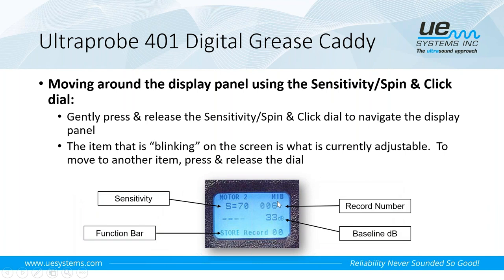And then across the top, where we see motor two, and then the MIB, or the motor inboard, this is the machine name and the point name. However we name the route or name our points in the software, when we load it into the Grease Caddy, however we name it there is how it will show up here on the display. So it will let us know at any given time where we are along the route.